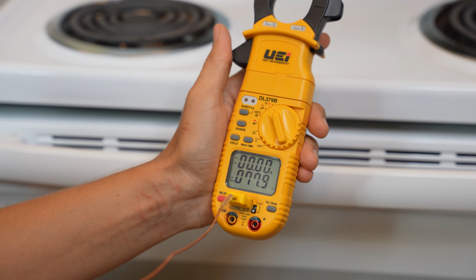The way I would normally test if an oven is heating properly or not is by using a multimeter with a K-type temperature probe plugged into it. This tends to be the most accurate way to get the reads and to see what's going on inside the oven. So instead of explaining what I do, I'm going to go ahead and show you an example of exactly what I would do to measure the oven temperatures to see if it needs to be calibrated or not.